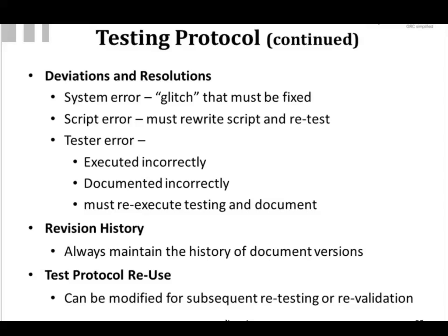If that's the case, as you are going back and updating your test protocol and your scripts, make sure you add that version as a new version of the document in the history. You should have a history log showing each version and why it was changed.